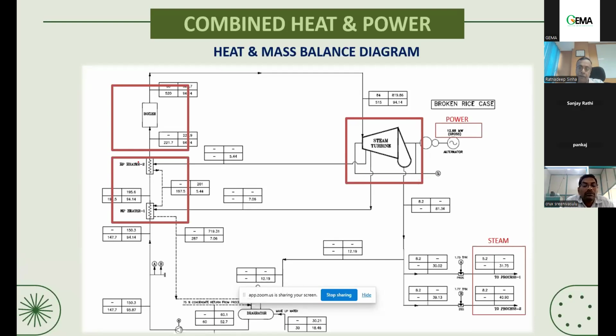See, this I have taken as a sample from a cogeneration plant where they are using broken rice, which is one of their feeds for the ethanol. And the megawatt can vary based on your power demand. That portion also is going to be covered in a particular webinar. And there will be a deaerator, which is basically a contact type feed water heater, and it is also required to scavenge oxygen from the system so that your boiler corrosion comes down.